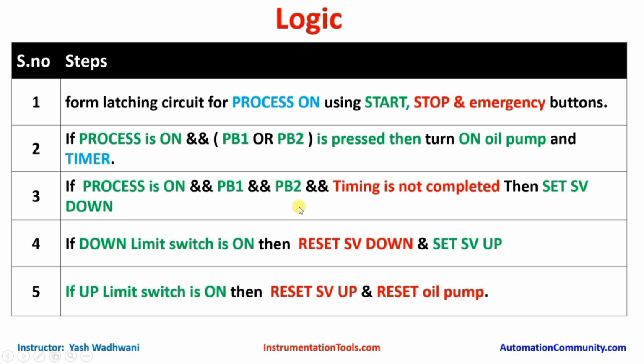We will understand the logic required to create our project. First of all, we have to create a latching circuit to know whether the process is on or off using start, stop and emergency buttons. After that, we will start our oil pump and timer when the push buttons are pressed. So for that, this is the logic: the process should be on, which is compulsory, and either push button 1 or push button 2 is pressed. So these two things are in series, but these two things are connected in parallel. If this condition is satisfied, then we will turn on our oil pump and our timer.